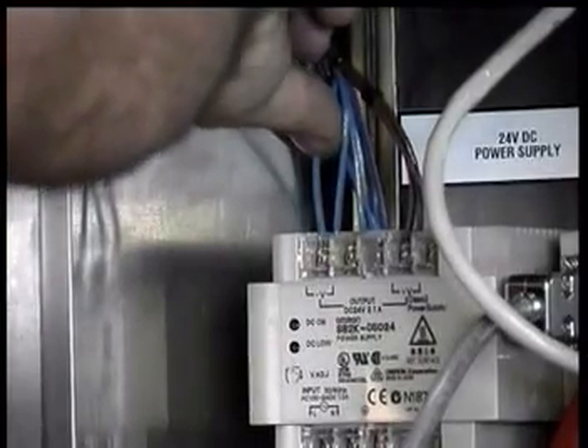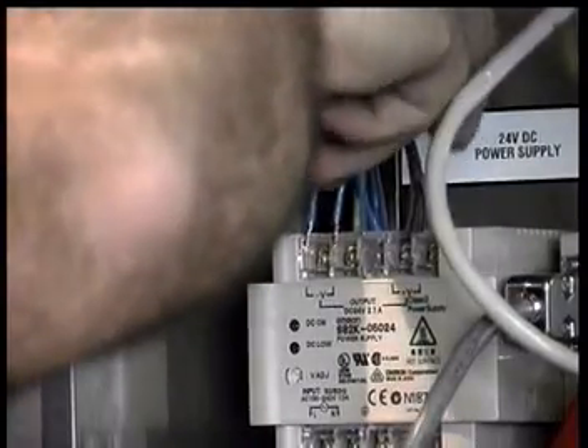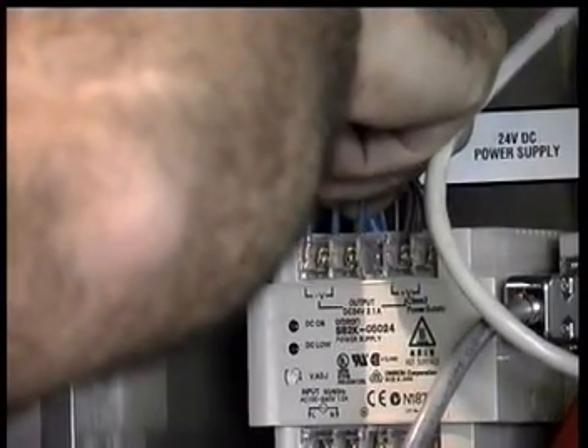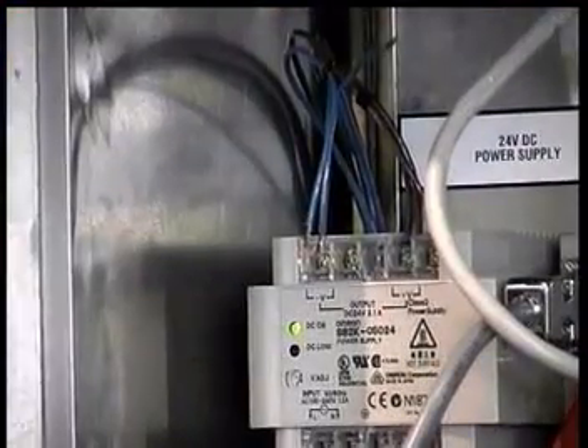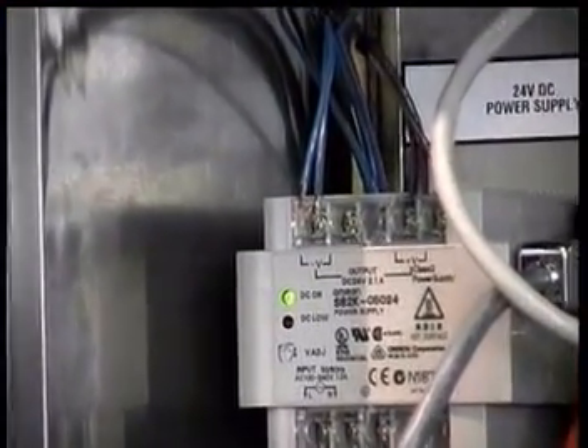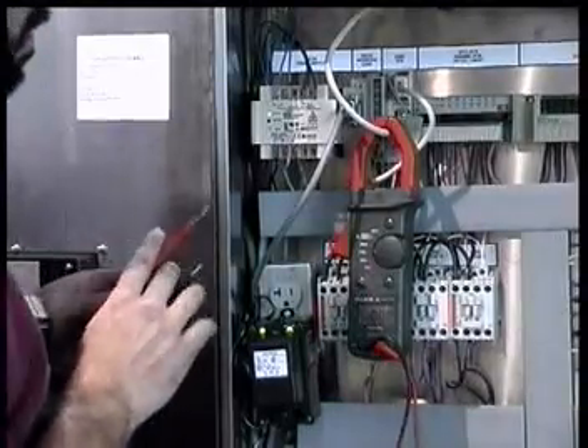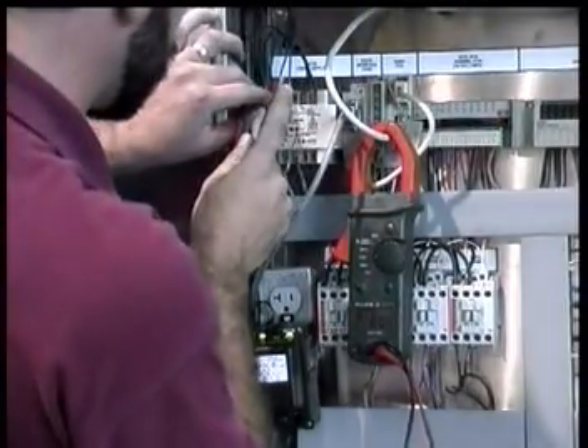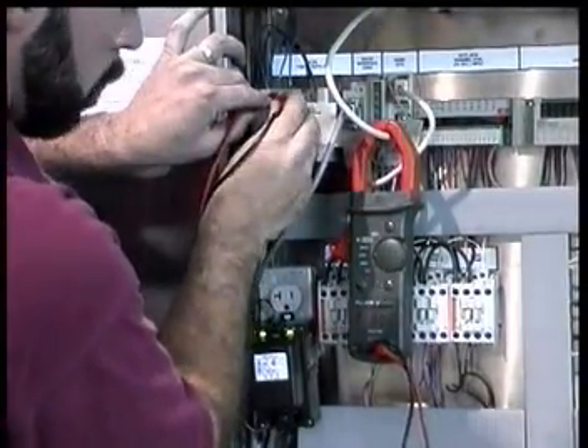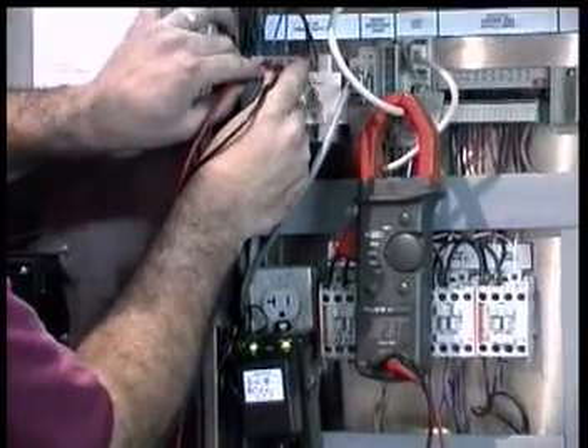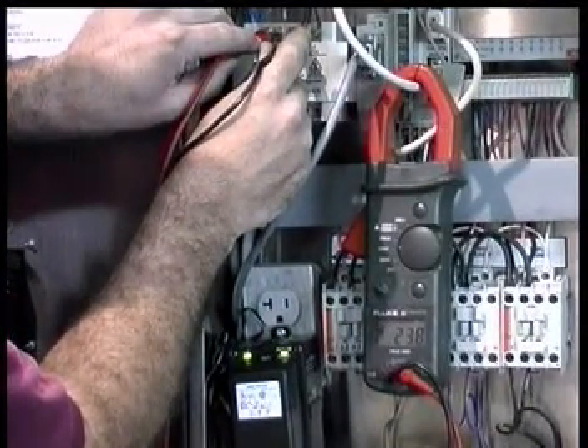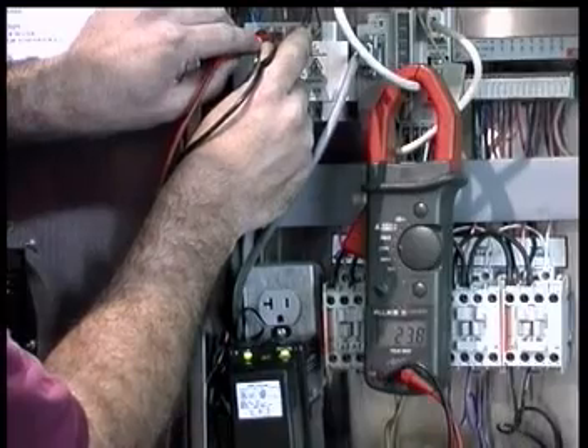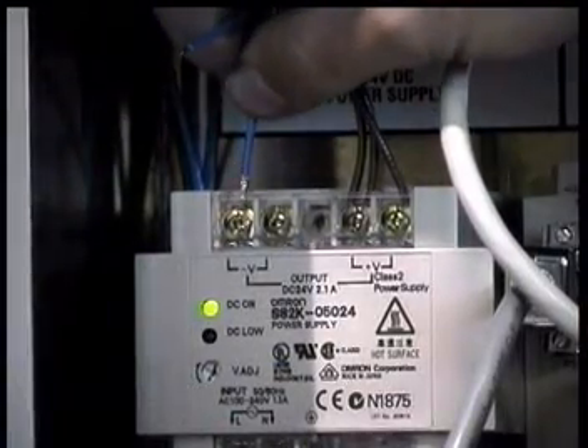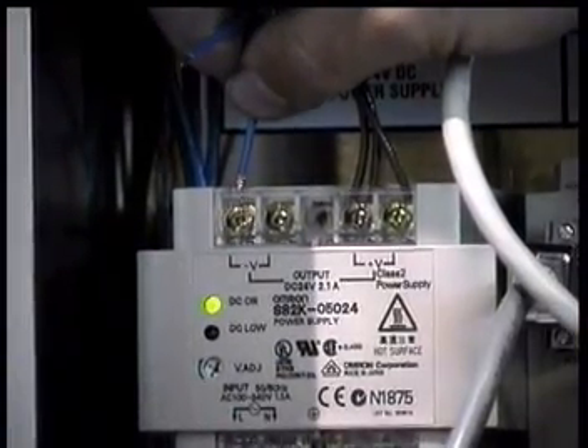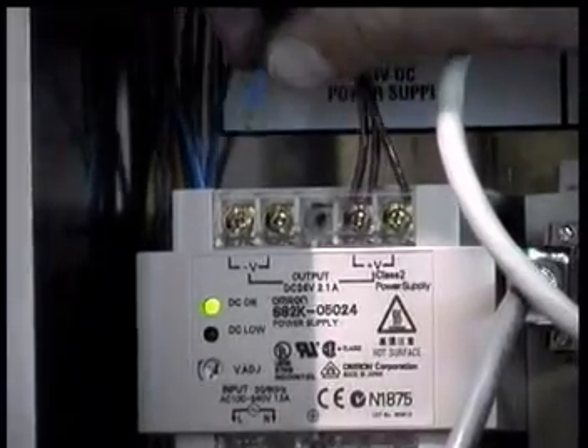If 110 is present, remove the blue wires on the top left-hand side of the power supply. Once the blue wires are removed, verify the DC power supply is operating correctly. Check for 24 volt DC power between terminals V negative and V positive. If 24 volt power is present, the problem is likely a short in a component associated with one of the wires or the wire itself. Reconnect the blue wires one at a time until power is lost again to determine which circuit is causing the problem.